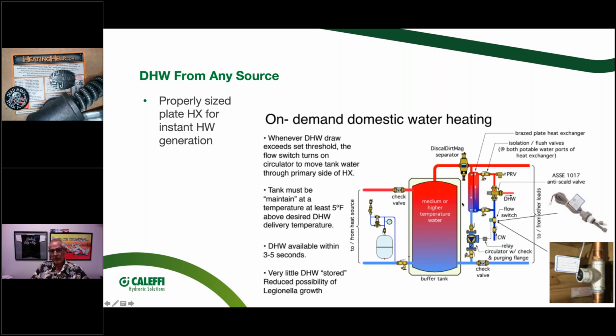And again, you've got it separated. You're not using this tank water to go out to your potable water, to your faucets. You're actually using the water as it flows through the plate heat exchanger. And that's really what's happening with the combi type of ModCons. Just think of this as the ModCon over here, and they'll just have a pump or a valve, or some have a little toggle valve in them that they can just, when you start flowing water, same thing, a low flow switch, I would say about a 0.5 GPM flow switch. So if you turn on just a little, maybe a lab faucet or something like that, you have enough flow there to trip on your pump and trip on your energy source.